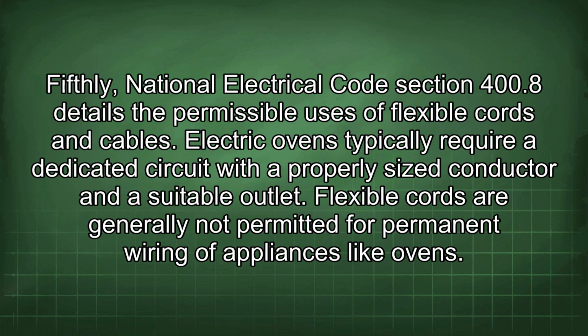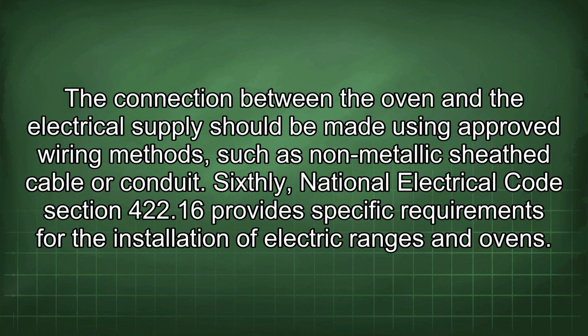Fifthly, National Electrical Code Section 400.8 details the permissible uses of flexible cords and cables. Electric ovens typically require a dedicated circuit with a properly sized conductor and a suitable outlet. Flexible cords are generally not permitted for permanent wiring of appliances like ovens. The connection between the oven and the electrical supply should be made using approved wiring methods, such as non-metallic sheathed cable or conduit.